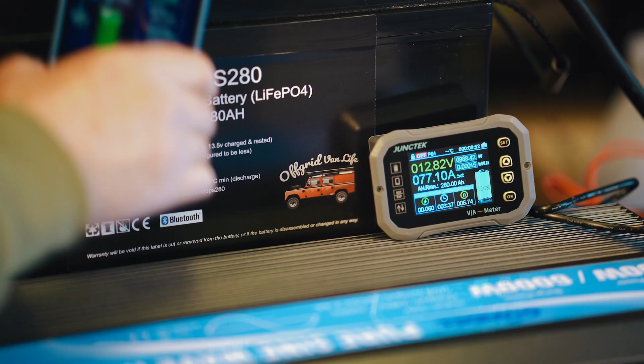I'm quite keen to see what my Victron Smart Shunt says. It's saying 74.6 amps, so slightly less. This is showing 77 amps, that's showing about 75 amps - not too bad, about a 2-3% difference, which is more than I'd want to see, but not too bad.